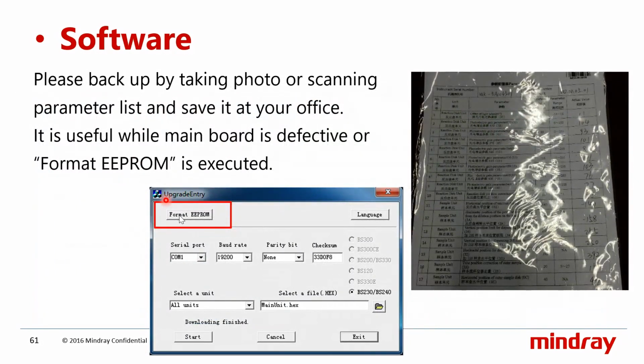Whenever you are formatting EEPROM, make sure you make a copy of these parameters. This sheet comes along with every instrument. It indicates how many parameters there are. For example, take the sample probe. What is the main position of the probe? The center of the cuvette. You don't have much adjustment play for the cuvette, right? Cuvette width is 5 mm, so the center of the cuvette is the main reference point. For the sample probe you have to adjust the cuvette area only. All other positions you can adjust with the motor steps.